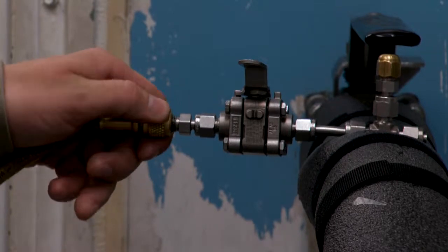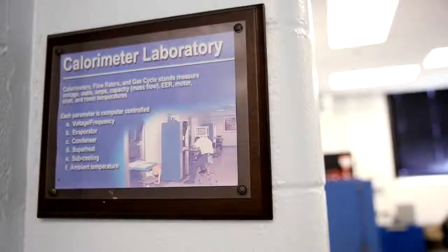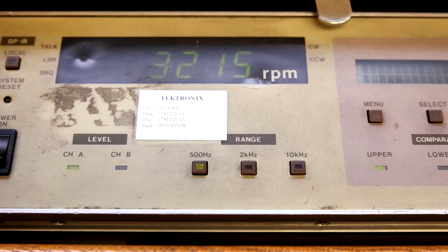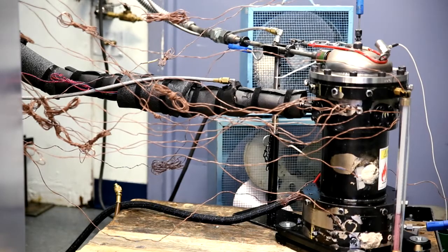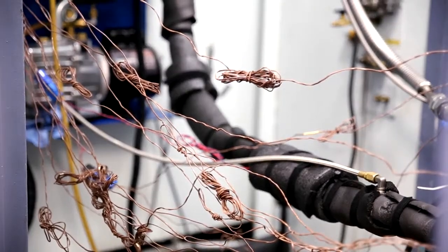We do a lot with recovery machines, vacuum pumps, and charging cylinders. I work on a calorimeter — a piece of equipment that helps us simulate ambient conditions. We're basically looking at how different models of compressors are going to work outside of the lab in a real world setting. When we test the compressor, we're looking at energy efficiency ratings, pressures, power intake, cooling capacity, and motor thermocouple temperatures.